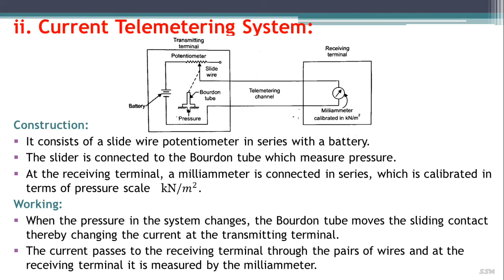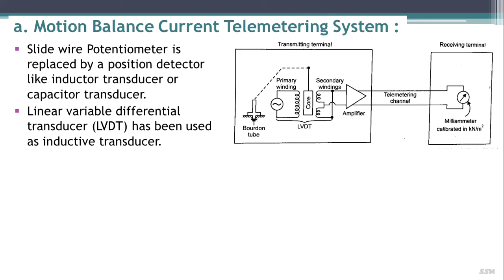So the improved versions of the current telemetric system we have nowadays are the motion balanced current telemetric system and the force balanced current telemetric system. We'll discuss these two. The construction is shown in the diagram. A slide wire potentiometer is replaced by a position detector like an inductive transducer or capacitive transducer. A linear variable differential transformer, LVDT, has been used as the inductive transducer.